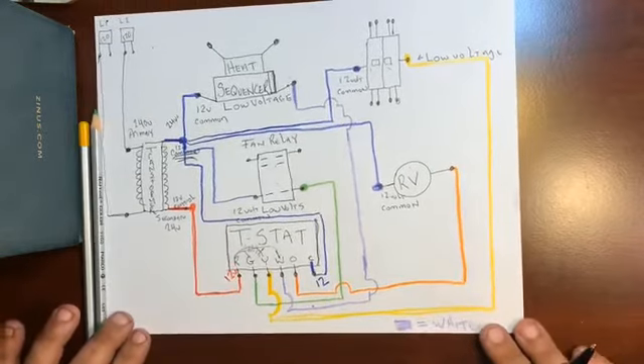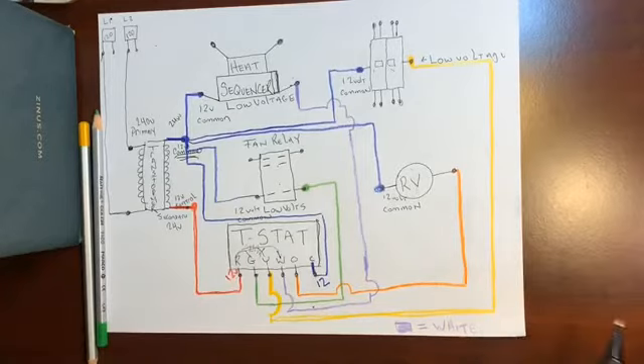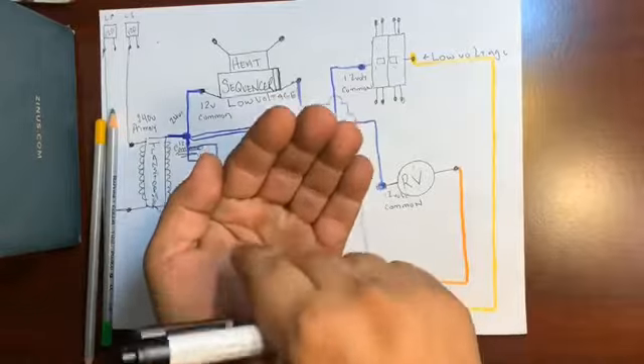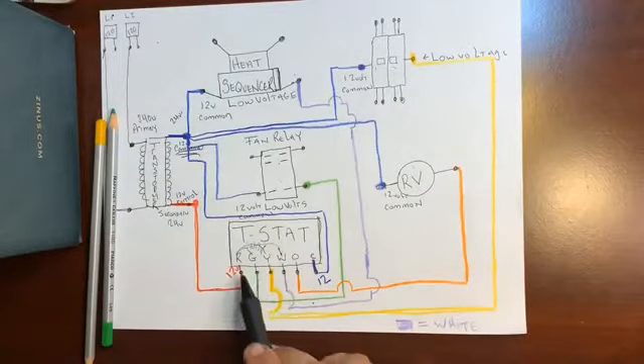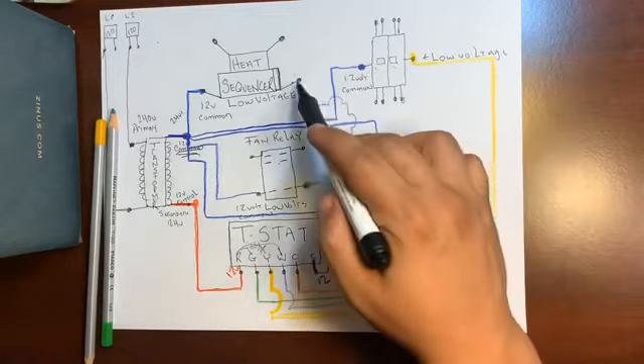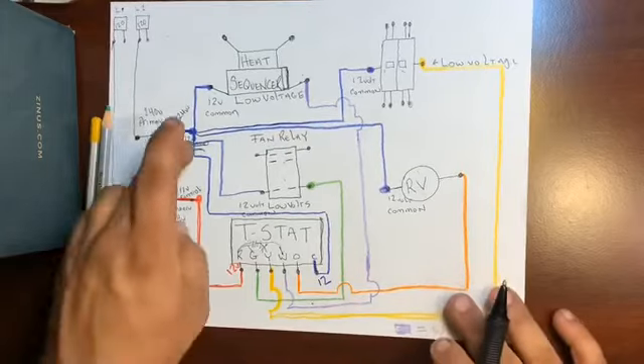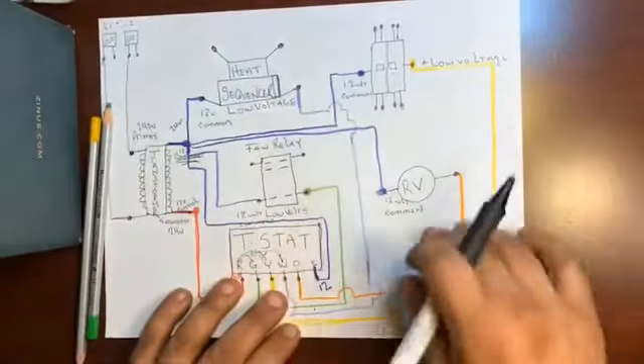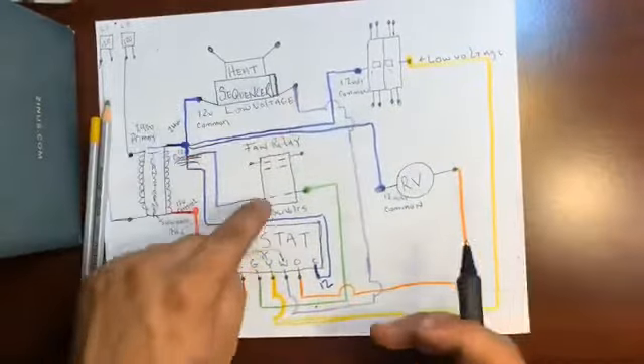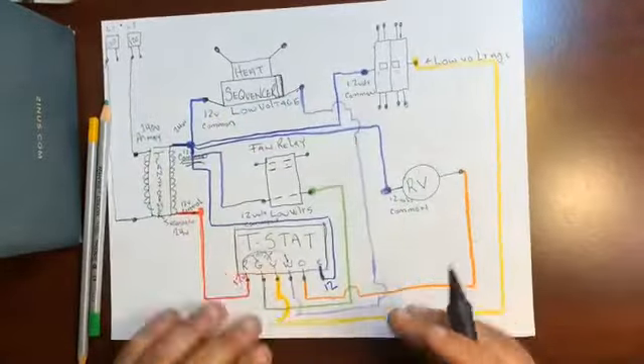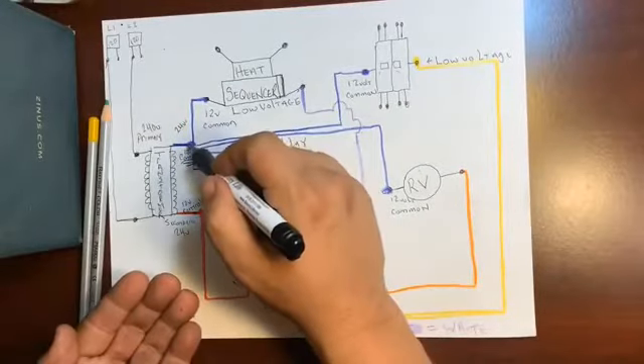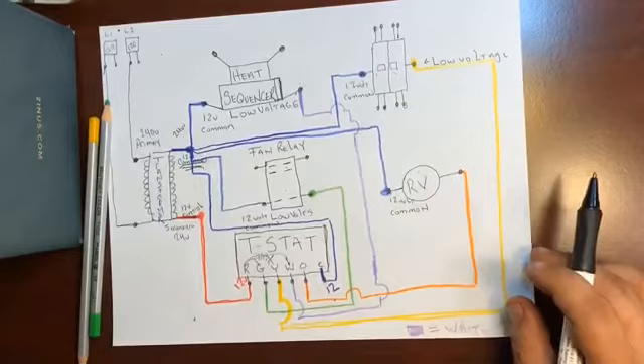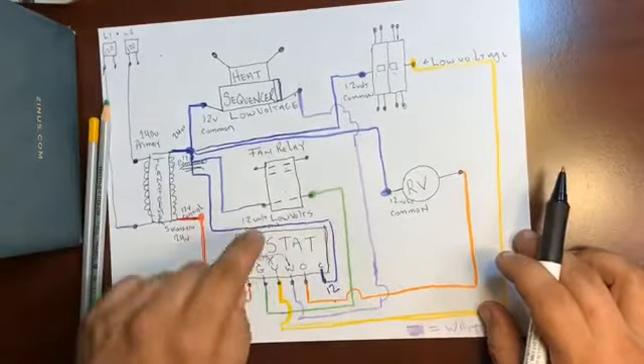This is the low voltage relay. We're gonna do it over and over again, but you have to understand, every single relay has 12 volt common in its hand. And then all the colors we talk about leave the thermostat to give it the other 12 volts to complete the 24 volts. And this is why I say common and control are so necessary to understand, because I could put 20 relays on this board. And if I put 20 relays on this board, we know each relay has 2 hands of low voltage, here and here. If I put 20 relays, you know that's 20 hands that are each gonna get 12 volts common. Nothing changes this. Every air conditioner that you come across is gonna be wired with the same controls. Absolutely, especially residential. Put the common in my hand.